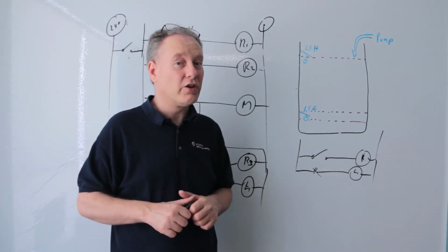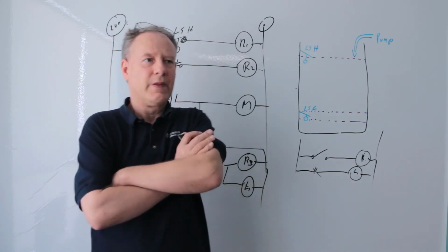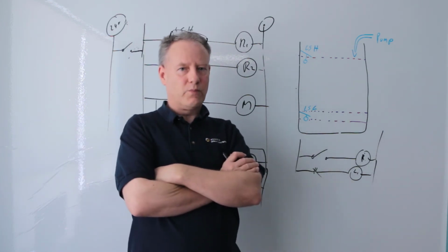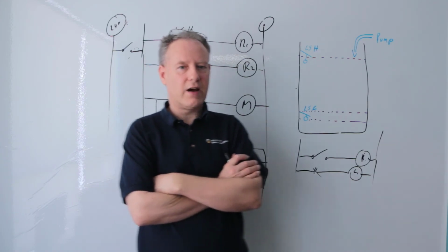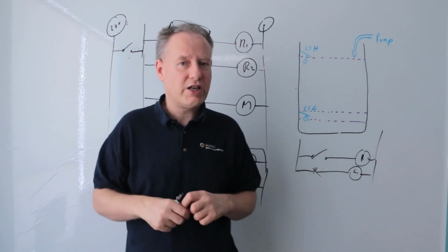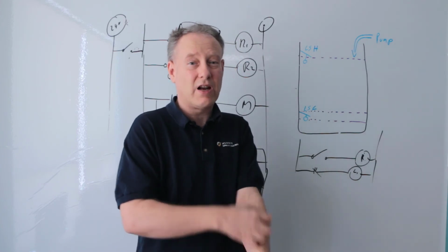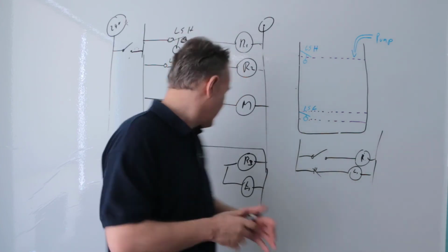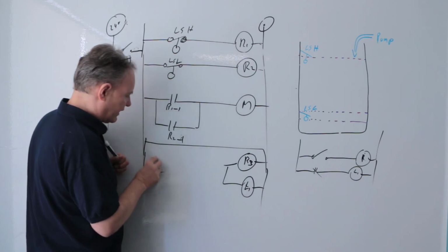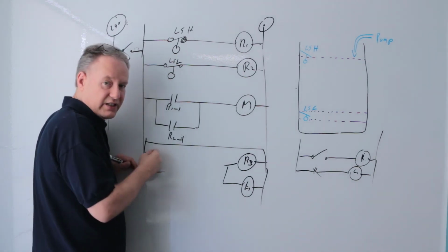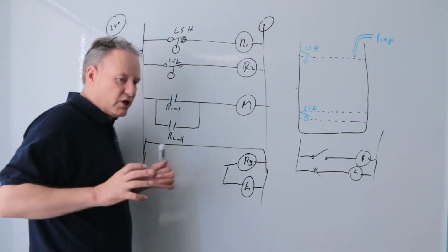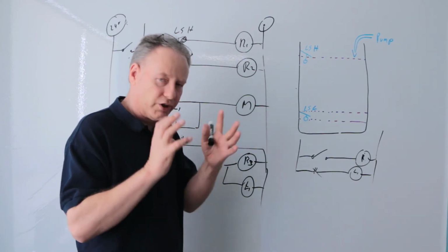I think it's probably a good idea. The reason is because if you've got some kind of error, you want to make sure that it shuts down so that someone has to pay real good attention to be able to go in there and fix it. So you may actually want to have kind of a lockdown situation where you put a contact in here to terminate the holding circuit, because you want to latch onto that event and say, no, I'm holding on to this event.